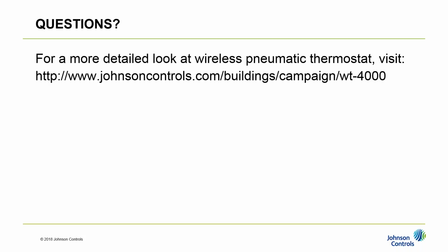Does the WT4000 itself act as a repeater? The WT4000 does not act as a repeater. The reason for that is mainly battery life. In order to be a repeater, you have to be constantly listening for transmissions to relay. So it's really only going to wake up every 5 minutes to conserve battery life. It continually monitors the pneumatic pressure on the lines at intervals of 30 seconds, but it will only transmit once every 5 minutes. If you do have a higher-priority command, like changing the set point, it will go faster than 5 minutes—it does that on demand instead of on intervals.